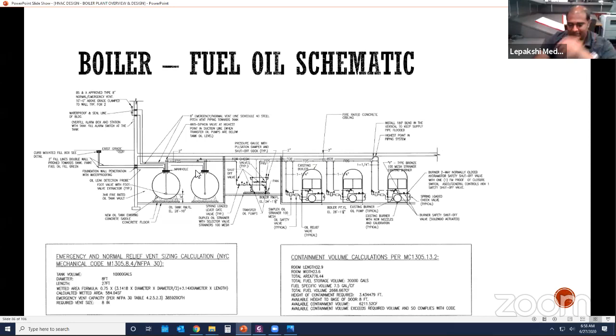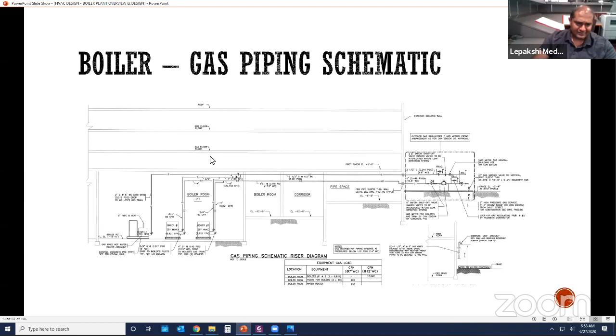This is a schematic of the gas piping. You'll have natural gas coming from the street, with safety valves installed. If there's a gas leak, it can be deadly, so you'll have gas leak detection systems with sensors that detect rising levels of methane or ethane. If detected, it shuts off the supply to the boilers—these are the safety valves. As shown here, there's a 6-inch safety shut-off valve, also called a Maxon valve, which serves that purpose. This is just a schematic to show you.